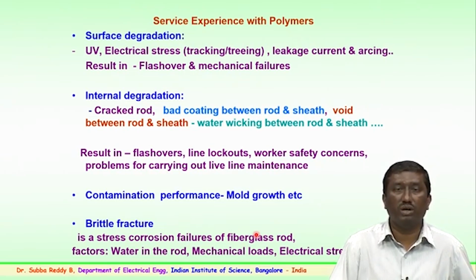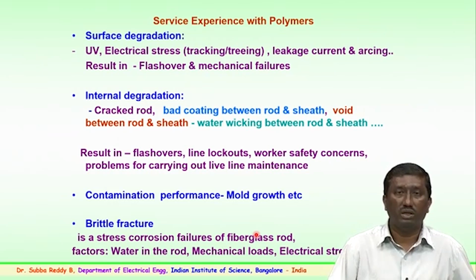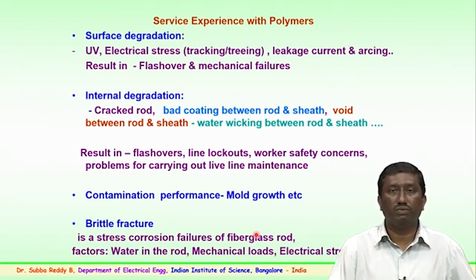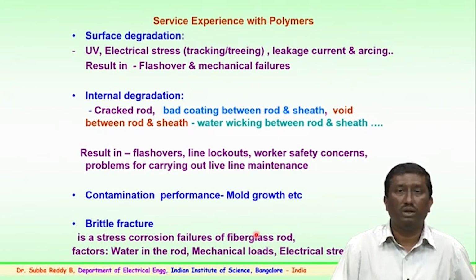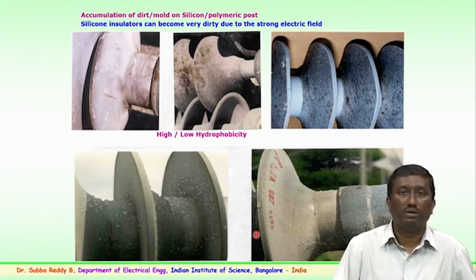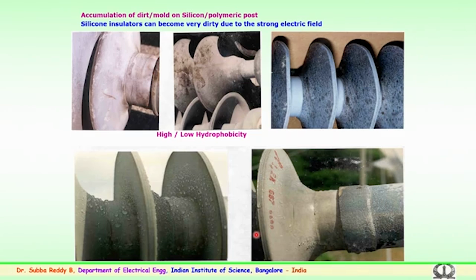And brittle fracture, again I was mentioning brittle fracture, this is a stress which has happened on the fiberglass rod, or a corrosion failure of the fiberglass rod. Factors could be water entering into the rod because of the mechanical load and electrical stresses, and the formation of nitric acid because of this moisture, and over a period of time this could lead to the fiberglass rod becoming brittle and the fracture taking place. A few of the experiments we have also carried out in the laboratory, and we will be demonstrating that in the future slides. Some of the early failures of polymer insulators which have happened in the field may be because of the accumulation of dust and mold on the polymer or silicone rubber post. Silicone rubbers could become very dirty due to the strong electric fields. You can see over a period of time the insulator becoming dirty and the surface getting rough, where water droplets start collecting and the failure could happen.